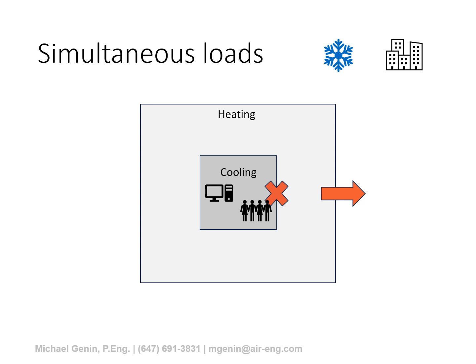And this is where you have an instance in which you are simultaneously heating the perimeter of the building and cooling the interior of the building. And so is there an opportunity to recover the heat between the two zones so we're not burning gas to heat the perimeter while running an electric chiller to cool the interior?